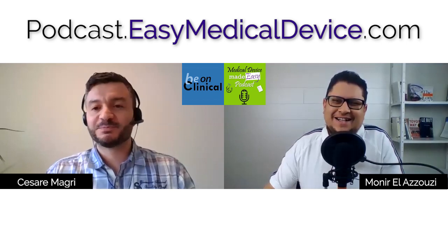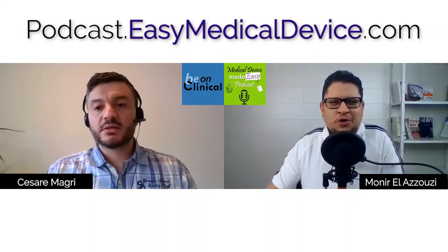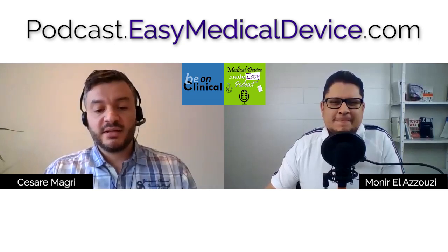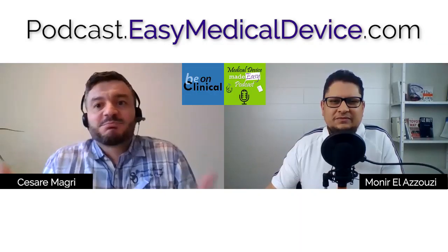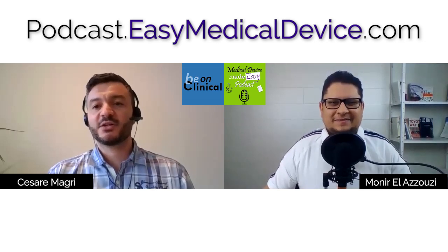I really like what you said, to clean the claims. So it's really great, to show that you really have to look at them and choose your words really carefully. I wanted to speak about it later, but the claim part is also where you can try to be extremely clear. Sometimes people think it's useless, but you can have a section called non-clinical claims, where you put everything that is a technical claim. Since you split it very clearly, the reviewer won't have problems understanding that handling and storing patient data is not something clinical, but just something your device does, that you want to have on a flyer, but for which you don't have to provide clinical evidence. It's going to be very clear.